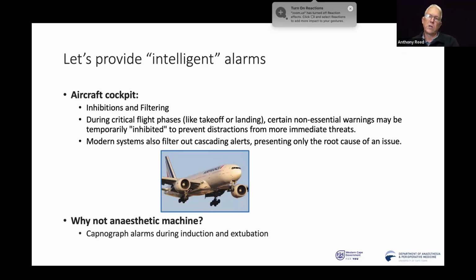And then the modern systems, not only do they stop alarms, but if alarms do occur, they don't set off a whole lot of them, because often when one thing fails, something else will happen as a consequence of that, and something else happens as a consequence of that. So you might have 3 alarms telling you about the same thing. They've also stopped that. For us, if you have an airway disconnect, we will lose CO2 and we'll lose airway pressure, and then the ventilator will tell us it's not ventilating. And actually, only one of those probably needs to go, and it's the root cause. So they've also worked their alarms so that they're much more intelligent than ours.